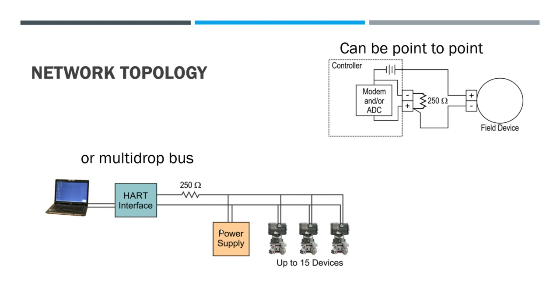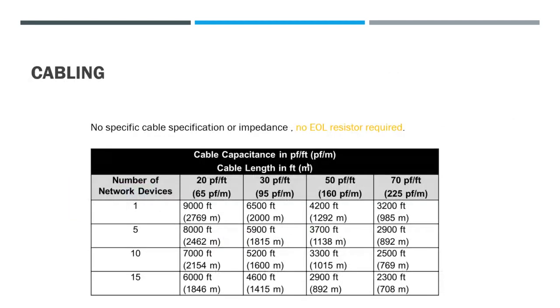Most industry standard power supplies are set to the point where they can only handle three or four devices at a time. So in a dedicated field bus HART network, you'd have to have a bigger power supply in order to run all 15 of the devices.